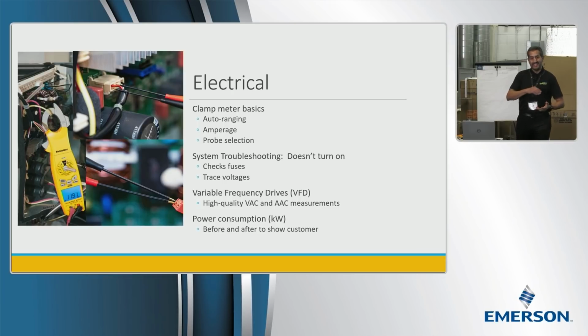Those systems take an AC voltage signal coming in, convert that AC signal into a DC signal, and then convert it back into an AC signal, typically a modulated AC signal, before it's fed into a compressor and a fan so those compressors and fans can vary their speed based on the load. Now, during that AC to DC to AC conversion, a lot of electrical noise is generated in that voltage signal. With a normal true RMS meter, you may not get an accurate voltage or current reading due to that noise.